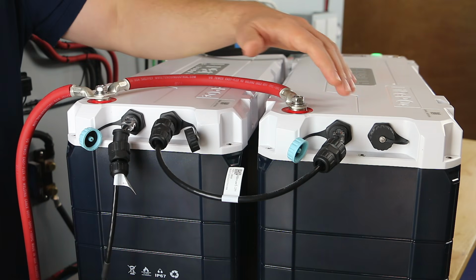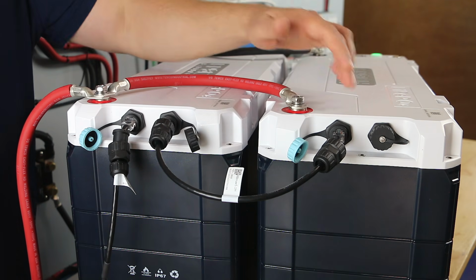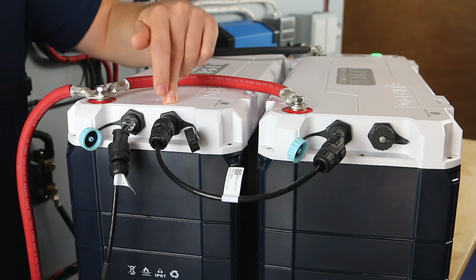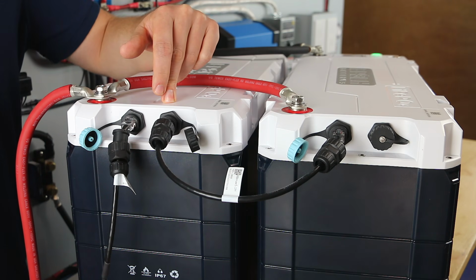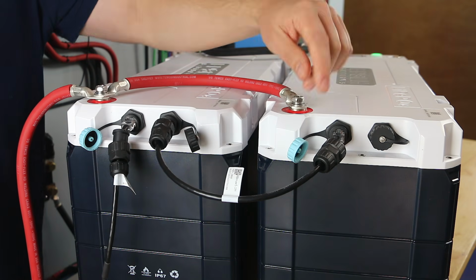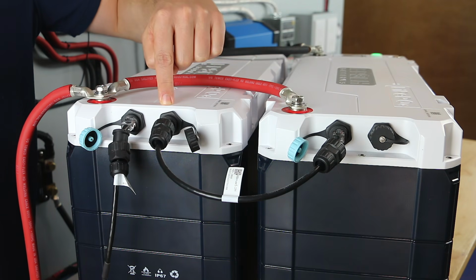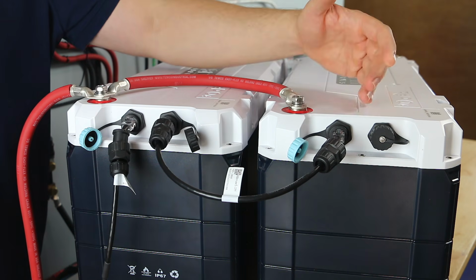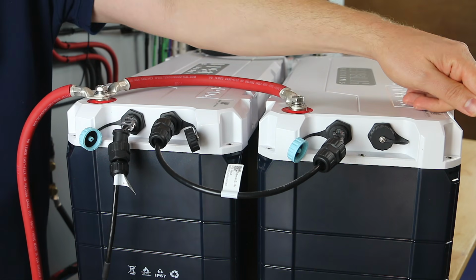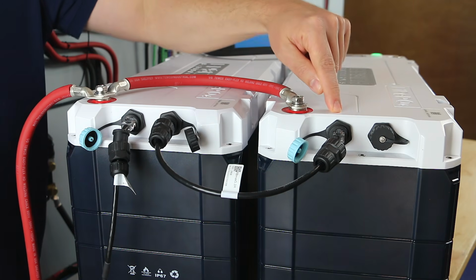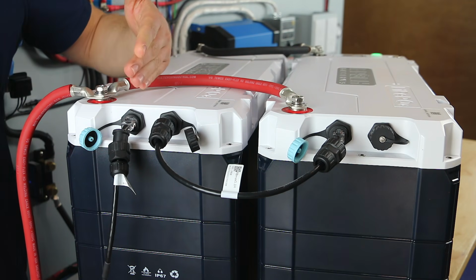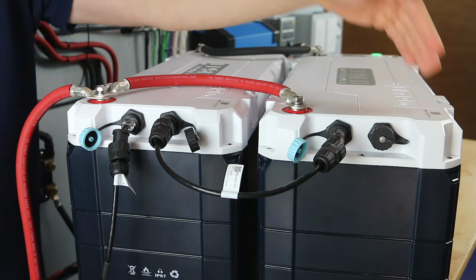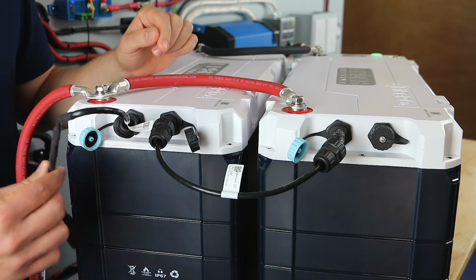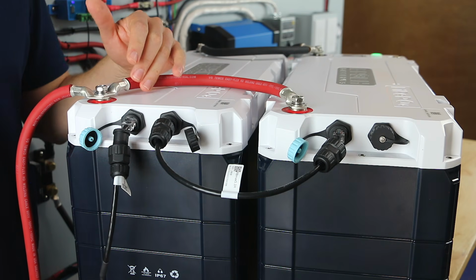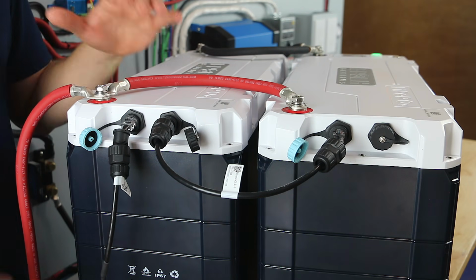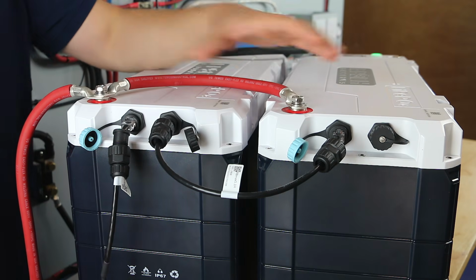As for the other connections, you can see this little jumper here between the slave battery, reporting that data into the master battery. If you had up to 15 slave batteries, you'd leave the blue port and come into the black port on the master. With each additional battery, you add another jumper, leaving the blue port and coming into the black port each time. That allows all those slave batteries to report their data down the CAN bus to the master battery, so the master battery can communicate that information with the larger Victron system. That's how you get the Victron comms set up properly.